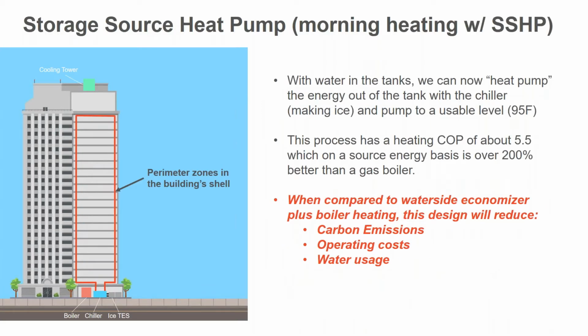So I've kind of termed this a storage source heat pump. We have ground source and air source and water source. Well, the source of the energy here, when we're doing the heating, is going to be coming from storage. So now the goal on a cold winter day would be somehow to capture as much waste energy as you can and have those tanks be fully water at the end of the day of your collection period of this waste energy.